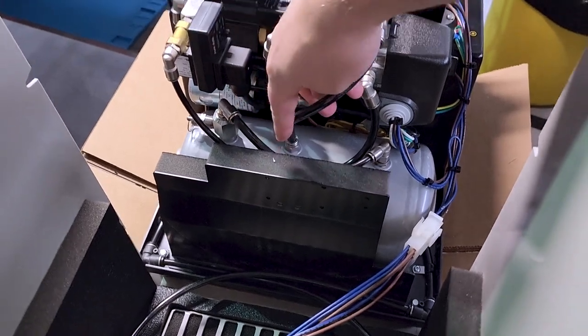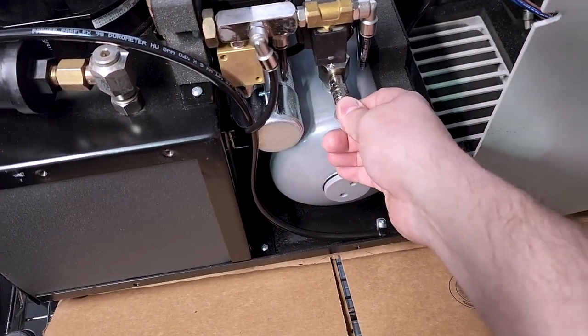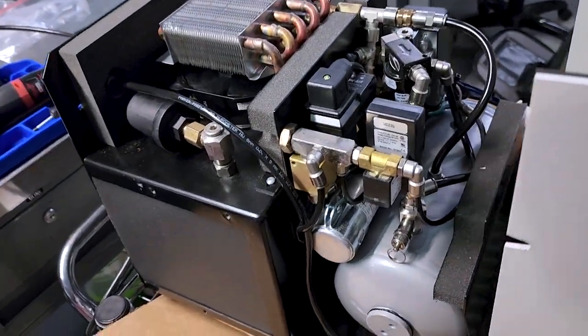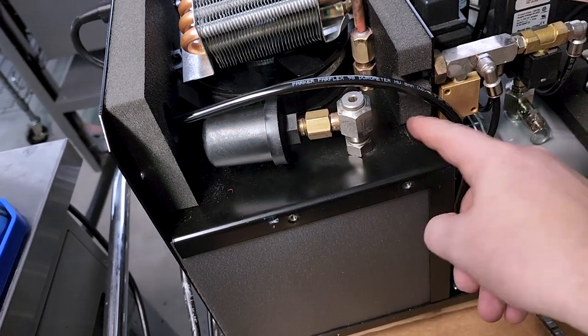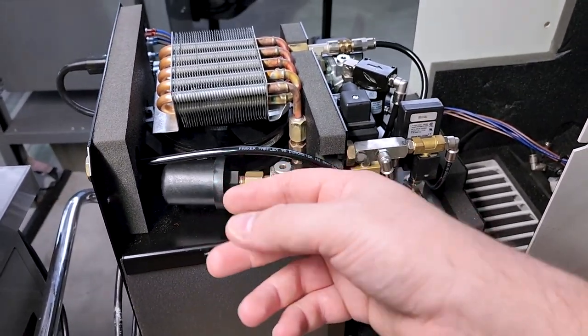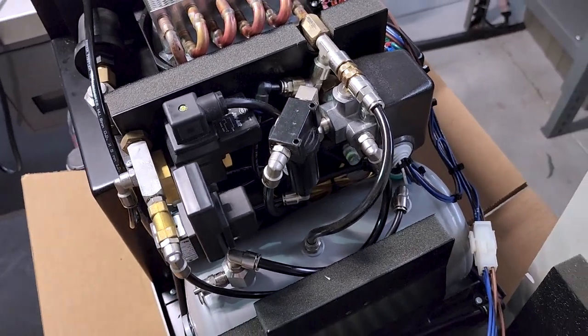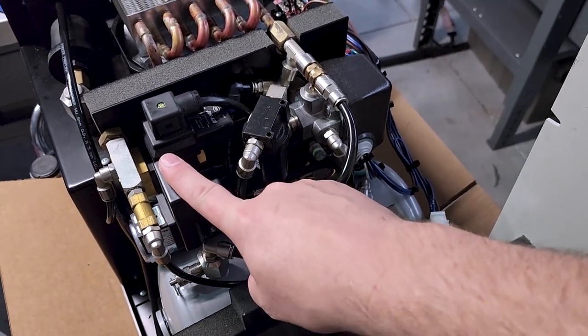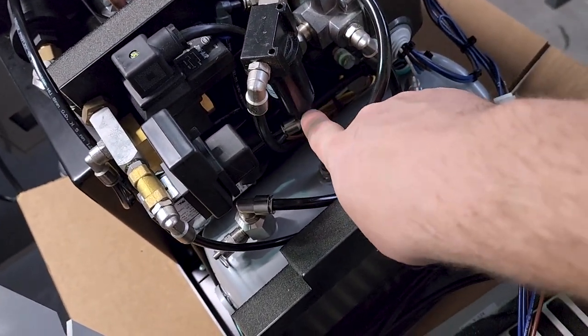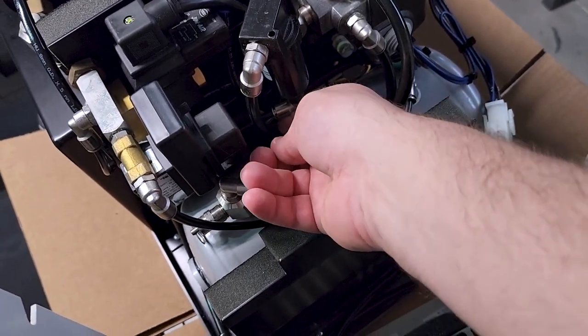So here you have a purge. So this guy here will come up to one of these guys. So it will purge and you have your safety valve right here, which you see I'm pulling on it. There's nothing going on there. You have a motor start run capacitor. I like how it's nice and accessible right here on the side. Very good. And over here, this is your input. So this is your incoming air. And that is a muffler. That is because your compressor, it oscillates the air and just the oscillation of the air itself generates excessive noise. So they added a muffler to the air input. So it's a pretty neat and simple device. It works on its own. And here you can see they have an auto purging water trap. It's right there. So you can see that it's plumbed. Very cool.